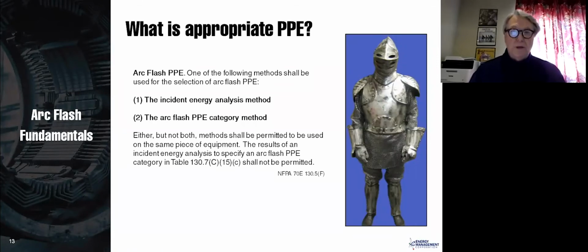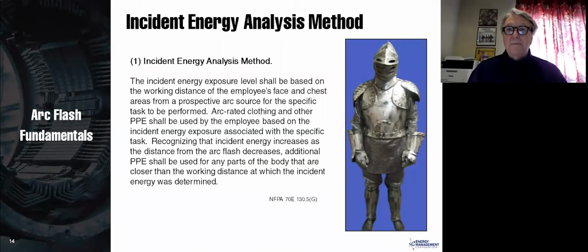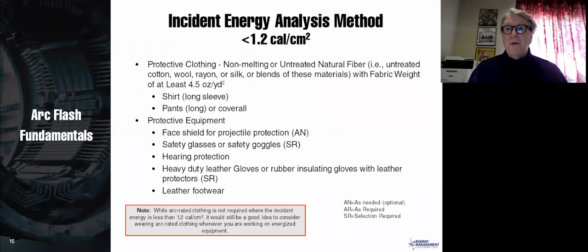And I'm just going to, we covered both of them last week. We're only going to cover the newer one this week. That's the incident energy analysis method. And the incident energy analysis method is based on calculating the calories at that point. So if the calories are under 1.2 calories per square centimeter, which is the level that will give you a second-degree burn, then you just need to wear non-melting long-sleeve shirt and pants and your normal protective equipment.